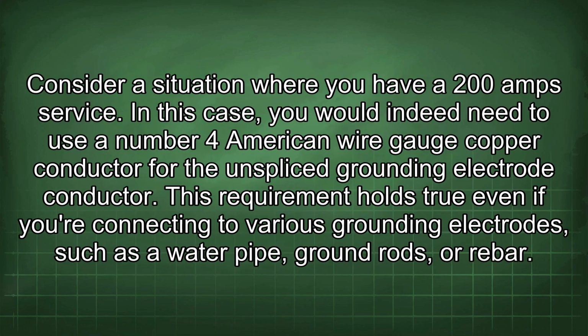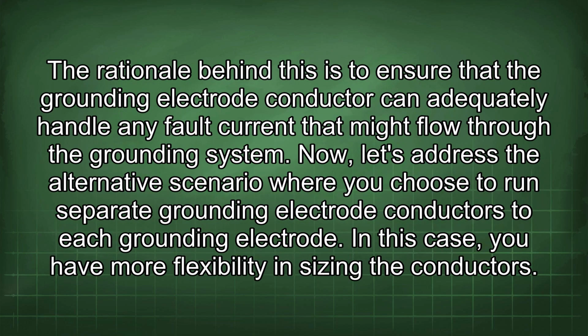Consider a situation where you have a 200 amp service. In this case, you would indeed need to use a number 4 American wire gauge copper conductor for the unspliced grounding electrode conductor. This requirement holds true even if you are connecting to various grounding electrodes such as a water pipe, ground rods, or rebar. The rationale behind this is to ensure that the grounding electrode conductor can adequately handle any fault current that might flow through the grounding system.